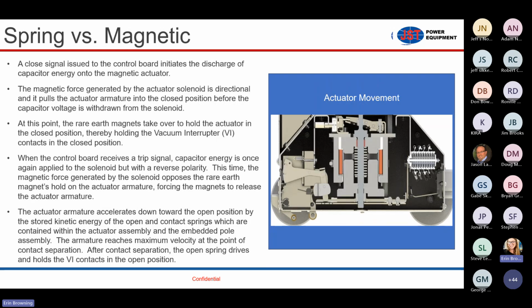I'm not going to get too much into the weeds on this, but I wanted to show you a little animation of how the actuator works. Basically, the orange segment is a cross section of that donut shaped coil that I asked you to visualize. And on top of that are permanent magnets. That's what these white things are. So basically, the permanent magnets hold this H-shaped piece that's moving up and down. This is the armature of the breaker. When the breaker is opened or closed, that H-shaped device is held constant. It's either held up or it's held down. And it's held up and down by the permanent magnets that are in the actuator.